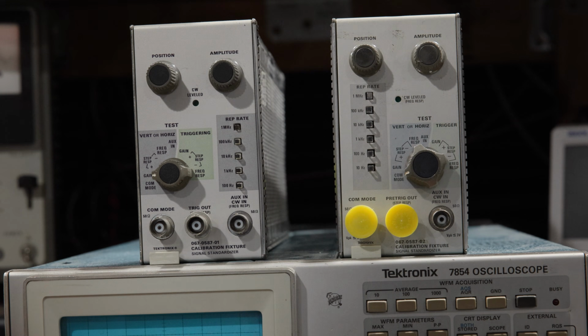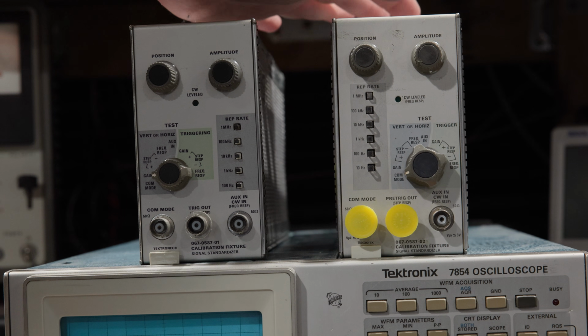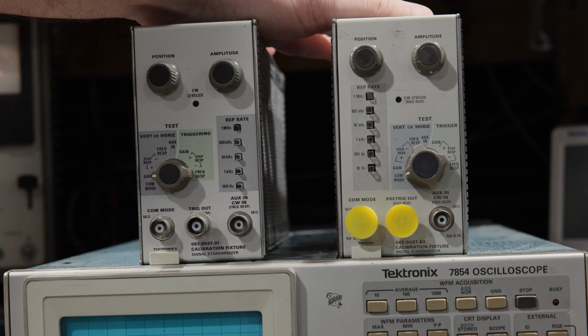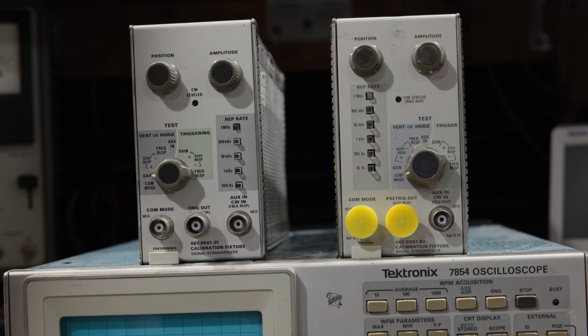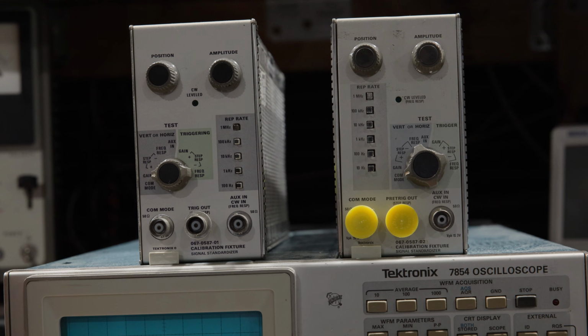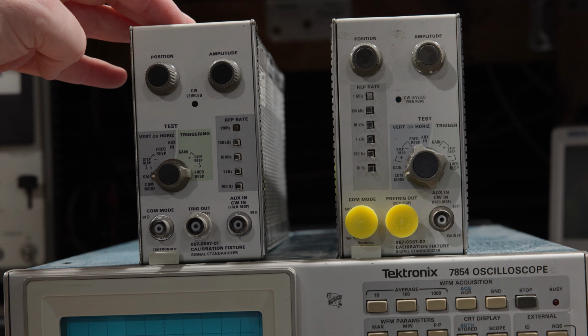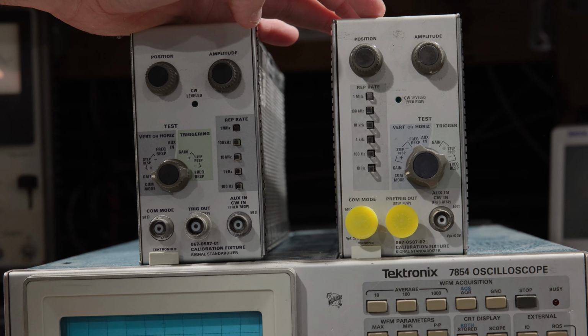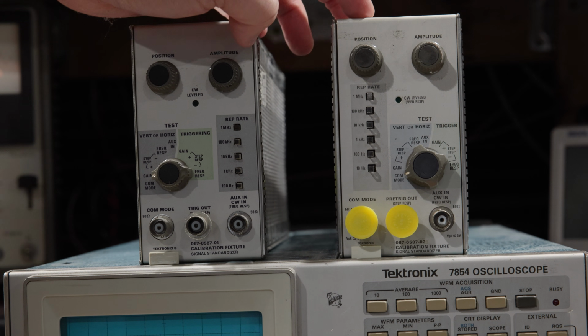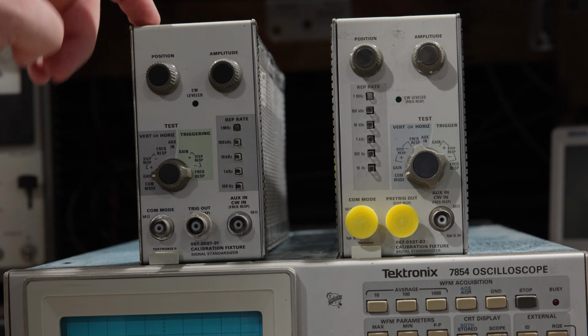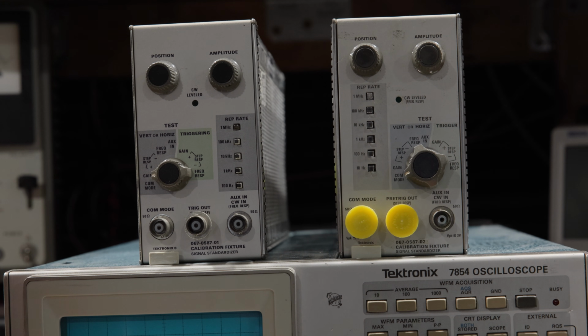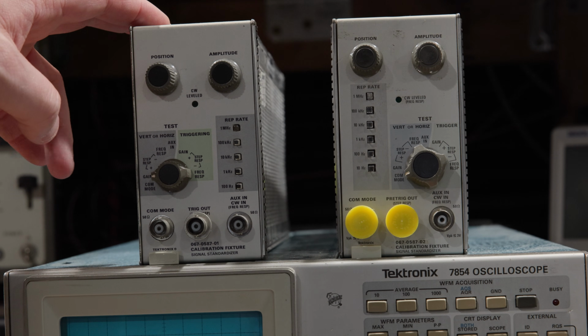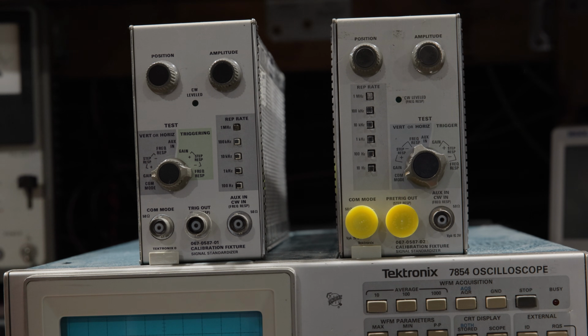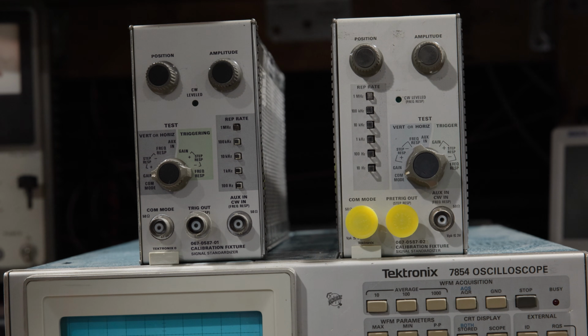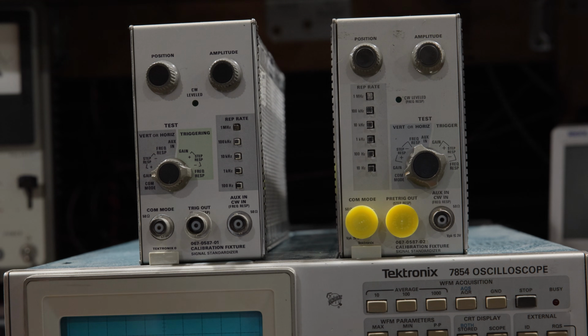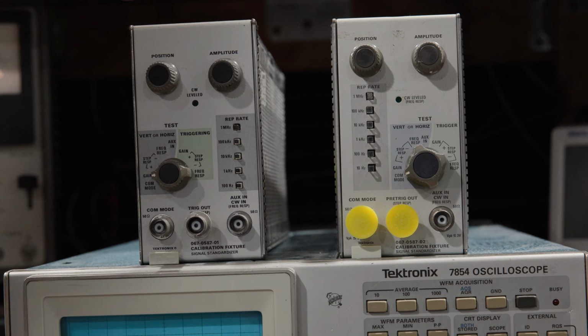So we have a -01 and a -02 calibration plug-in for the 7000 series. One of the things that's a little strange with these is the -01 is the 500 megahertz, the -02 is the 1 gigahertz plug-in. This is far more rare than the -01. Theoretically, if you had to push it, you could do the calibration with two of these -01s. You just wouldn't have some of the higher end bandwidth of the -02. The calibration document does call for two of these.